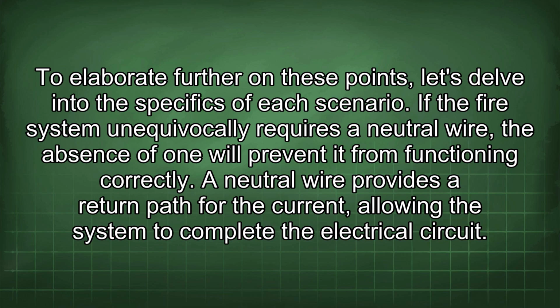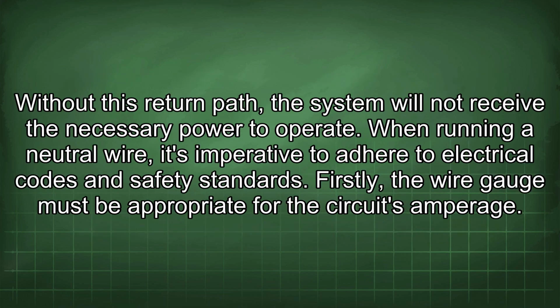If the fire system unequivocally requires a neutral wire, the absence of one will prevent it from functioning correctly. A neutral wire provides a return path for the current, allowing the system to complete the electrical circuit. Without this return path, the system will not receive the necessary power to operate. When running a neutral wire, it's imperative to adhere to electrical codes and safety standards. Firstly, the wire gauge must be appropriate for the circuit's amperage.